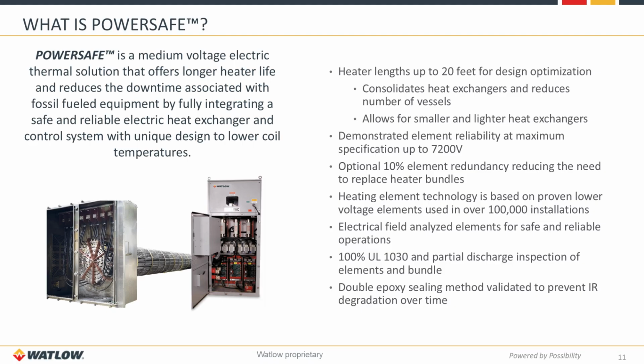Some of the POWERSAFE features include heater lengths up to 20 feet for design optimization, fewer vessels and consolidated heat exchangers for streamlined installations, demonstrated element reliability up to 7200 volts, optional 10% element redundancy to minimize bundle replacements, heating element technology that is based on proven low voltage elements used in over 100,000 installations, electric field analyzed elements for safe and reliable operation, 100% UL 1030 and partial discharge inspection of individual elements and entire bundles. And finally, double epoxy sealing to ensure electrical insulation remains robust, even in humid environments.